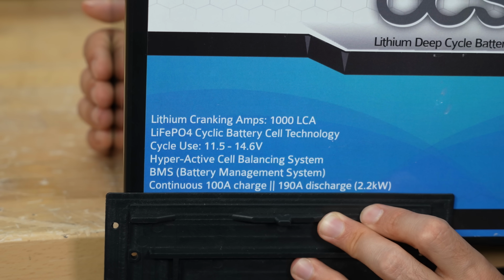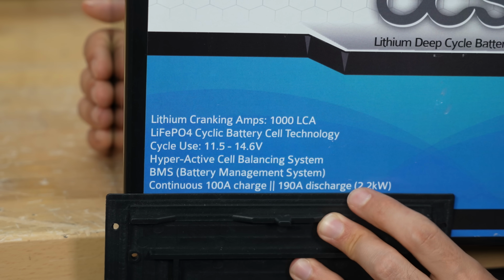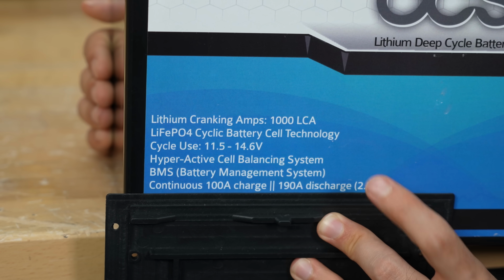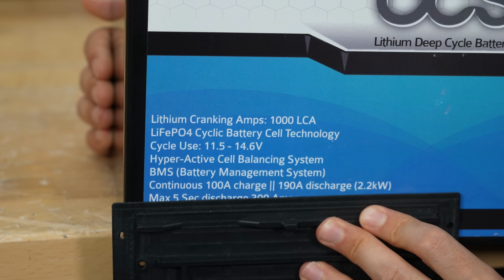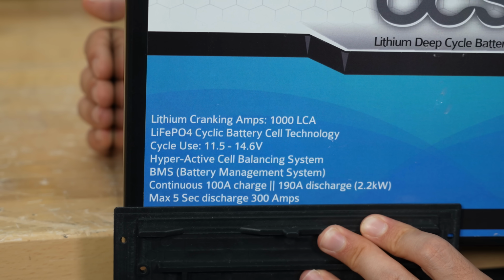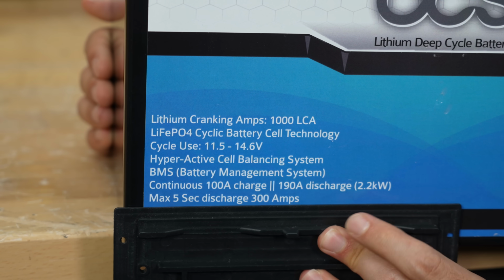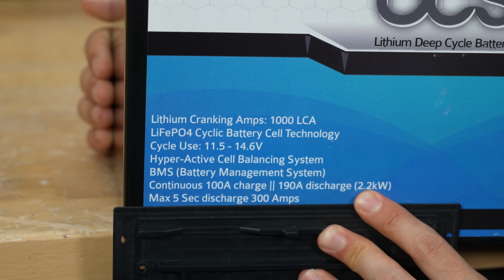Next, continuous 100 amp charge and 190 amp discharge, so that's what we're going to be testing today. And the last line is a max of 5-second discharge with 300 amps, and I have a load tester to see if it can actually pull that off.